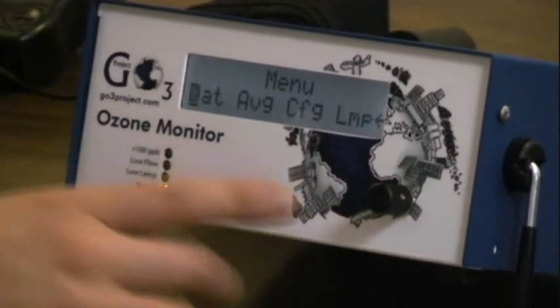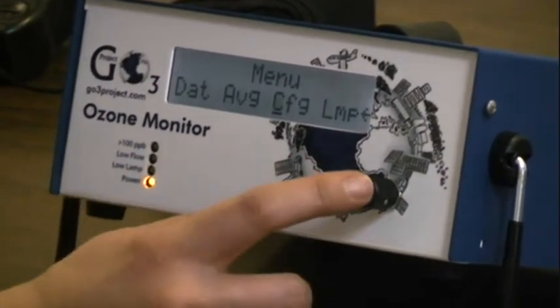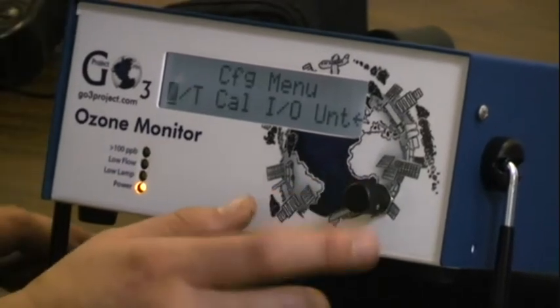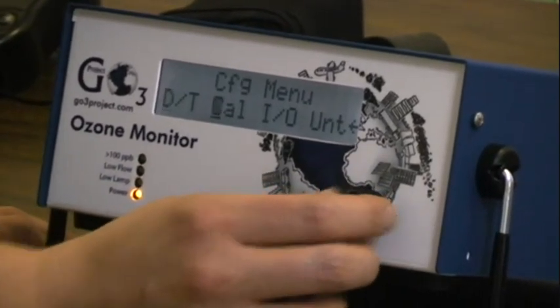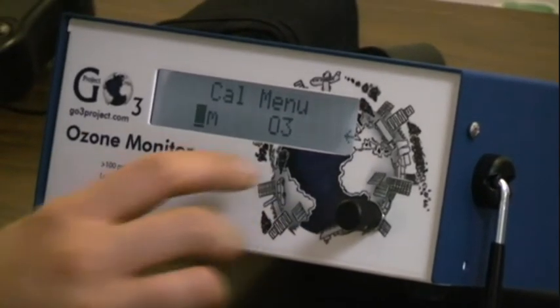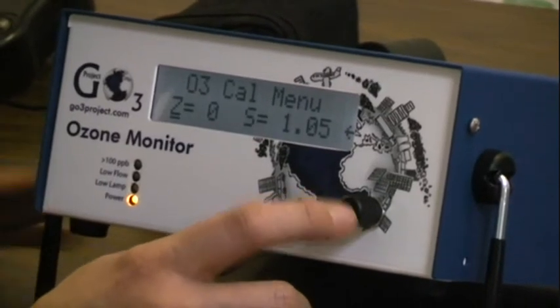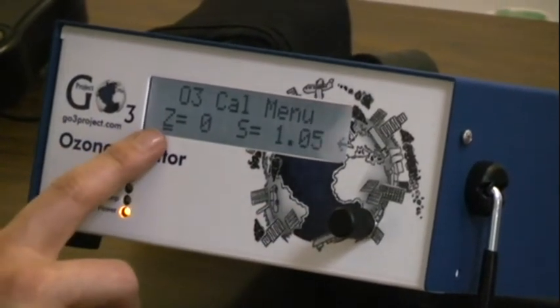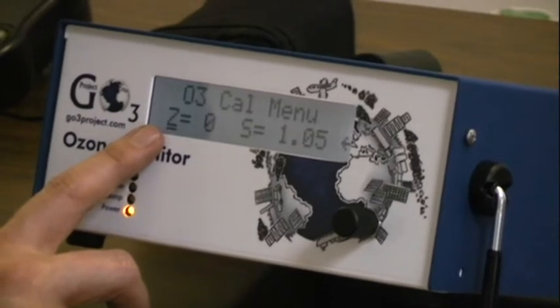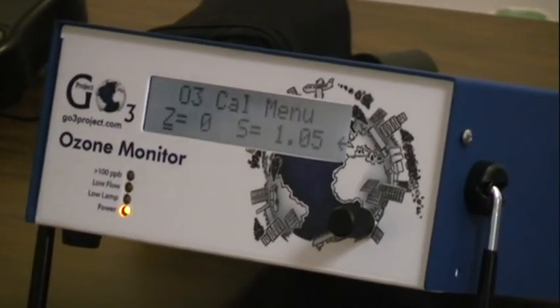You're going to go into the menu, over to CFG, click once. Go into CAL, C-A-L, click once. Go over to O3, and this Z is the offset. So this ozone monitor's offset is zero.